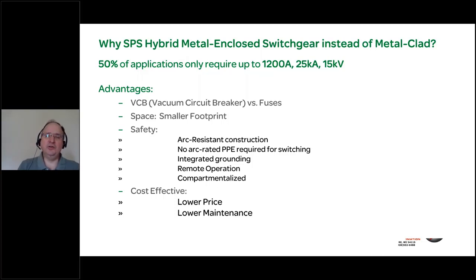In terms of safety, numerous advances in safety. Arc resistant construction for the disconnect switch itself. The disconnect switch, as you'll see, is a Schneider Electric component. There is no arc rated PPE required for that switching operation, even when standing right in front of the switch. It's an arc-rated enclosure. The third item is integrated grounding. So we eliminate both the risk and time and effort involved in the exposed energized task of grounding, and the grounding operation also becomes a no PPE operation with this type of equipment.